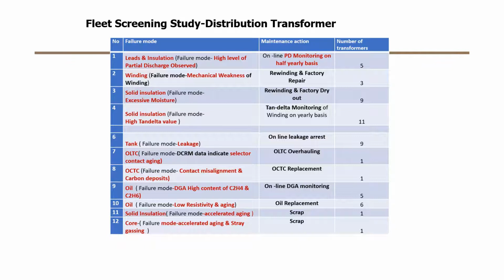For example, say you have one type of transformer in 100 numbers, and you categorize FMEA and find that 50 out of 100 have the same failure trend, or same kind of aging trend, or same kind of problem. That gives very good input to the system that we need a change in specification, or change in quality, or whatever it is, and what risks are behind it and what proactive action you have to take. So FMEA is very good for that.